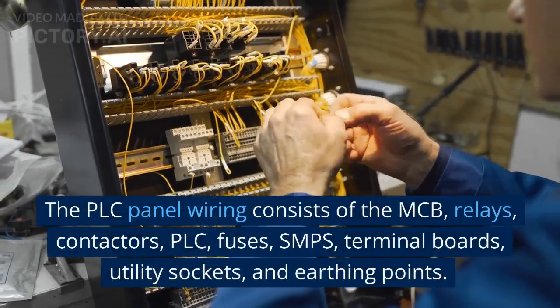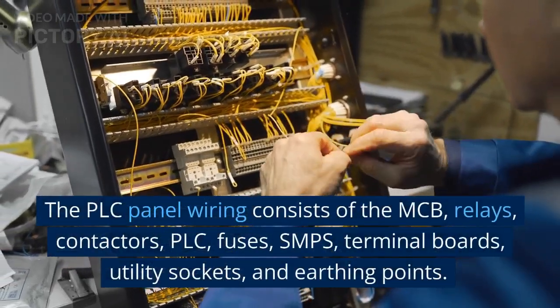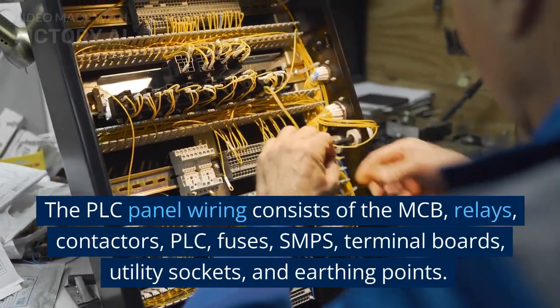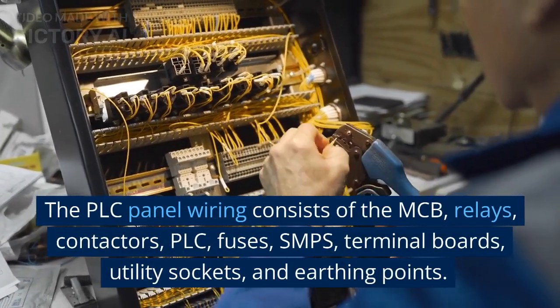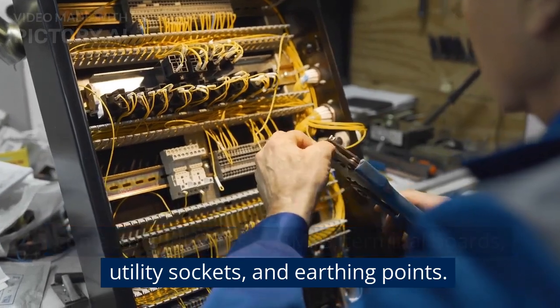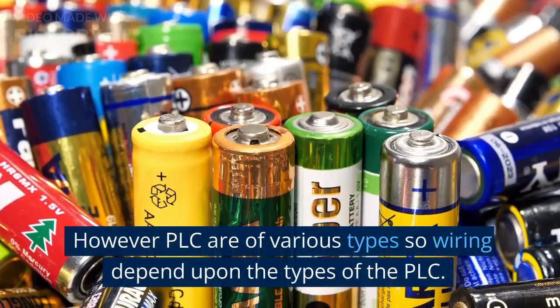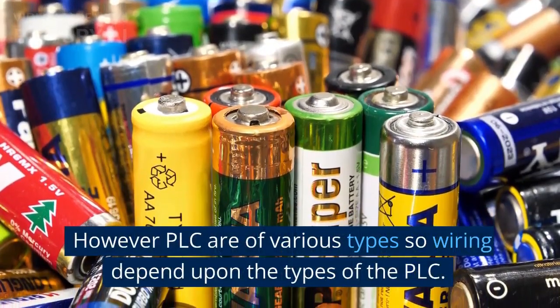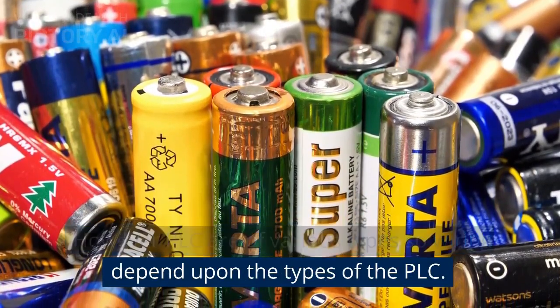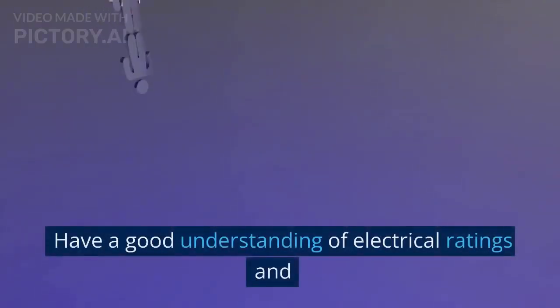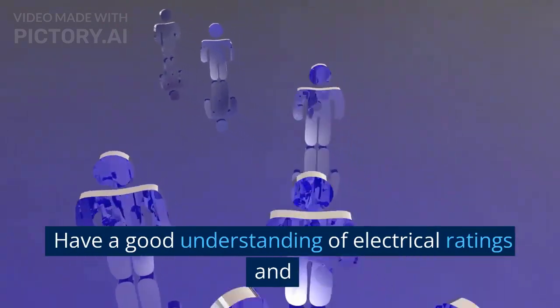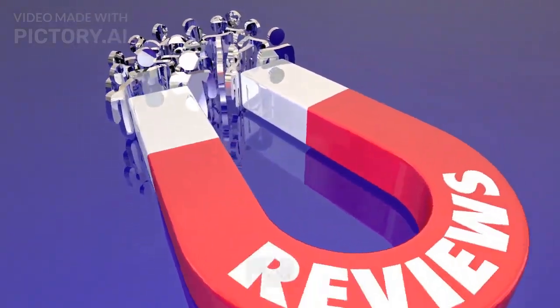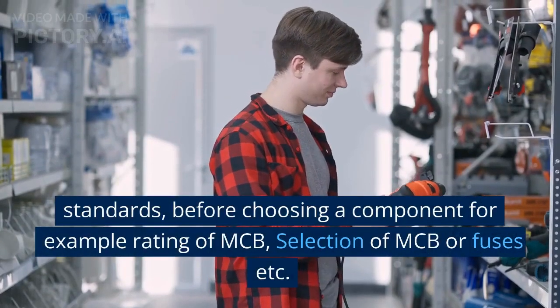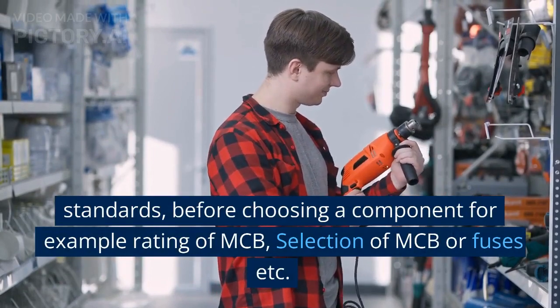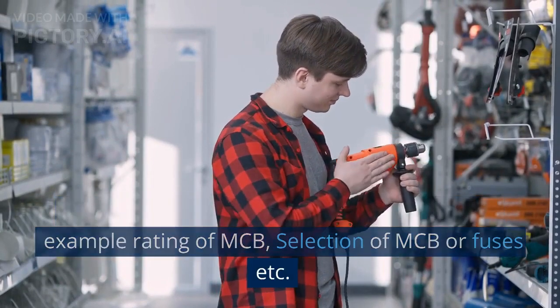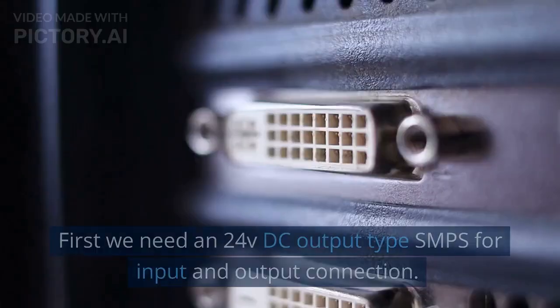The PLC panel wiring consists of the miniature circuit breaker, relays, contactors, PLC, fuses, SMPS, terminal boards, utility sockets, and earthing points. However, PLCs are of various types, so wiring depends upon the type of the PLC. Have a good understanding of electrical ratings and standards before choosing a component, for example the rating and selection of MCB or fuses, etc.